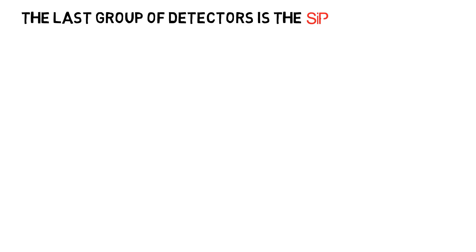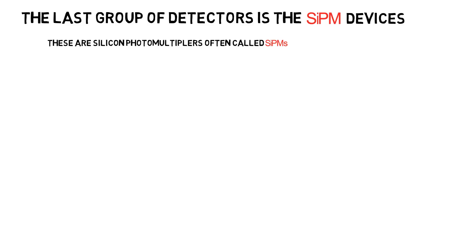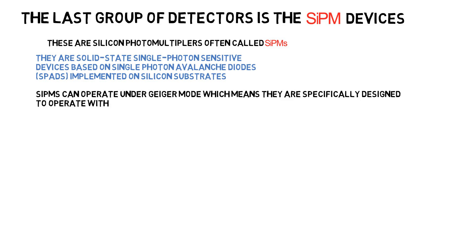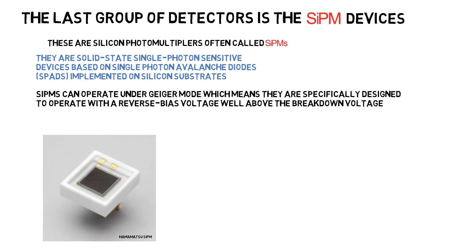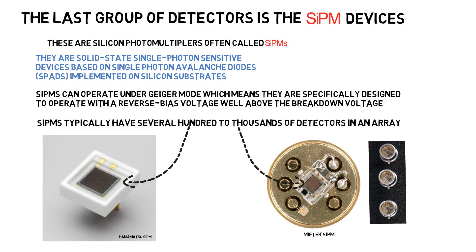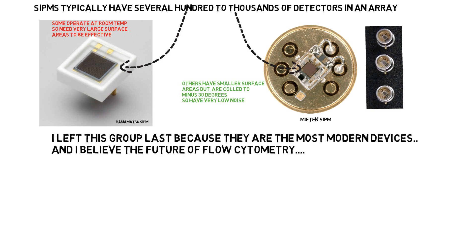The last group of detectors is the SiPM devices — silicon photomultipliers, often called SiPMs. They are solid-state single-photon-sensitive devices based on single-photon avalanche photodiodes, often abbreviated as SPADs, implemented on silicon substrates. SiPMs can operate under Geiger mode, meaning they are specifically designed to operate with a reverse bias voltage well above the breakdown voltage. SiPMs typically have several hundred to thousands of detectors in an array. I left this group for last because they are the most modern devices, and I believe they represent the future of flow cytometry.